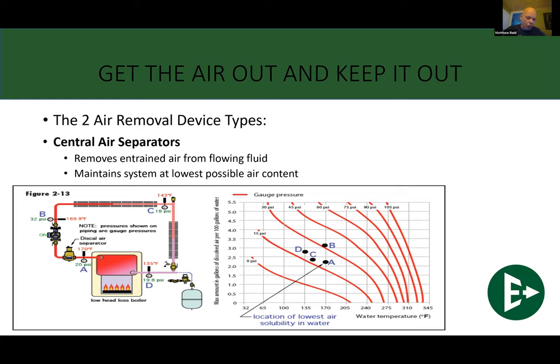If you were to put a pot of water on the stove to boil without a lid on it, you'll notice that you see your air start to come out of that water very, very quickly as soon as you start heating it up. And that's exactly what we're talking about. So hottest water, lowest pressure. On the suction side of the pump, you're going to have that air. It doesn't want to mix into the water. It wants to come out of the water. Great place to get it out. So do stuff like that, and you're going to have all sorts of success with getting air out of the system.